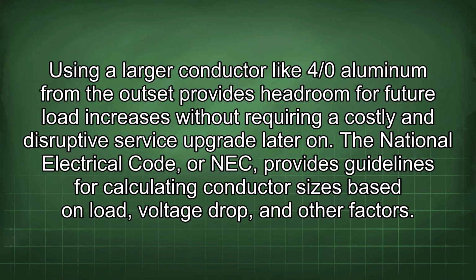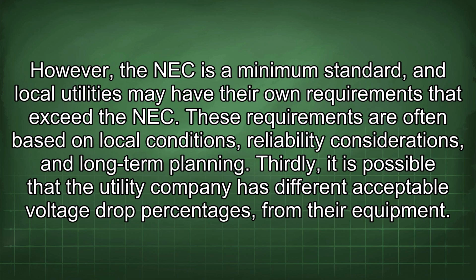The National Electrical Code, or NEC, provides guidelines for calculating conductor sizes based on load, voltage drop, and other factors. However, the NEC is a minimum standard, and local utilities may have their own requirements that exceed the NEC. These requirements are often based on local conditions, reliability considerations, and long-term planning.